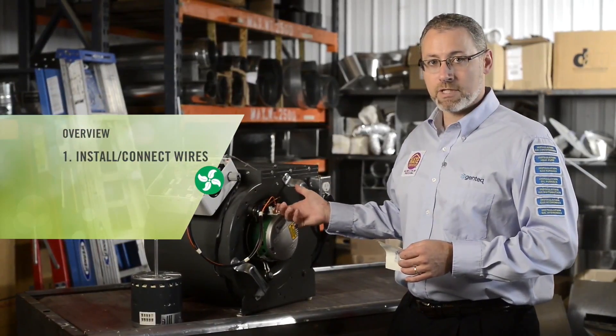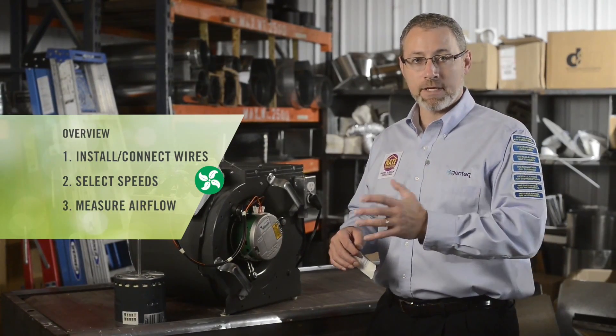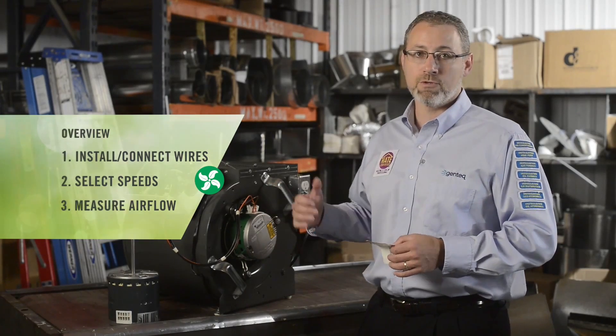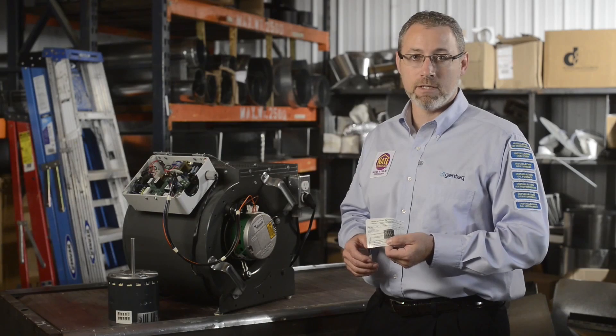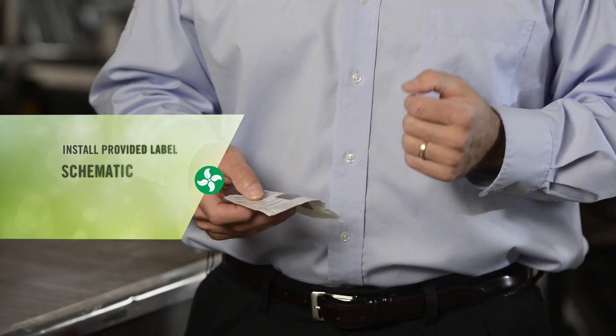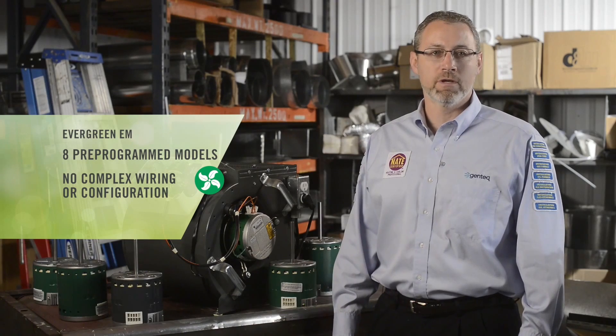To overview the installation of the Evergreen EM: we've installed the motor, connected the wires from the X13 into the Evergreen EM, and selected the correct speed in our HVAC system for our heating and cooling demands by measuring airflow and making adjustments. This is best industry practice whether we're using a universal replacement motor or an OEM motor. Last but not least, we highly recommend you take the supplied label out of the motor box and install it next to the unit schematic, writing down the horsepower of the motor that you replaced — this provides the next technician the schematic for the universal replacement product and the 800 tech support number if needed.